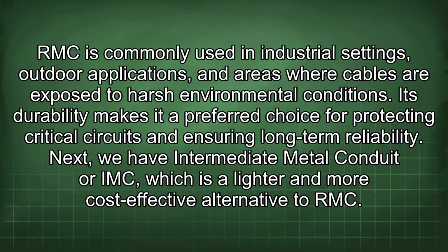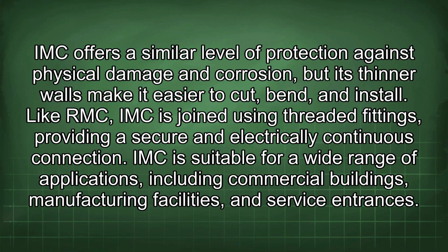Next, we have intermediate metal conduit or IMC, which is a lighter and more cost-effective alternative to RMC. IMC offers a similar level of protection against physical damage and corrosion, but its thinner walls make it easier to cut, bend, and install. Like RMC, IMC is joined using threaded fittings, providing a secure and electrically continuous connection.